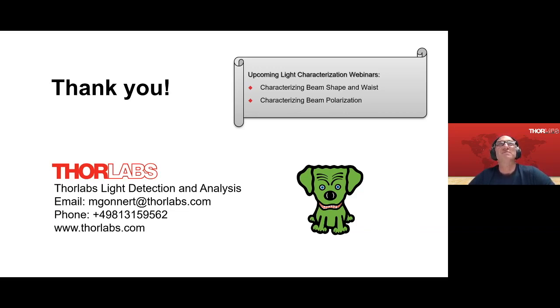Okay, thanks. Another question also concerning the damage threshold is, what is the relationship between the laser-induced damage threshold, LIDT, and the pulse width of a laser pulse? I think this refers to the fact that you have only mentioned a rough guideline for CW lasers being at around 100 milliwatts per square centimeter.